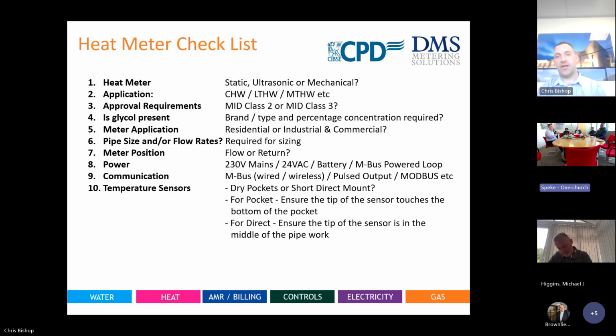Yet again, chilled, LTHW, medium temperature hot water. We need to know what we're dealing with regarding that network, what temperatures, and what is best to then select in relation to static, ultrasonic or mechanical. Approval requirements, class 2 or 3. Yes, we'll still have that question. People are still aware of class 3. Some people still don't know the difference between 2 and 3. That's all linked to points 1 and 2.